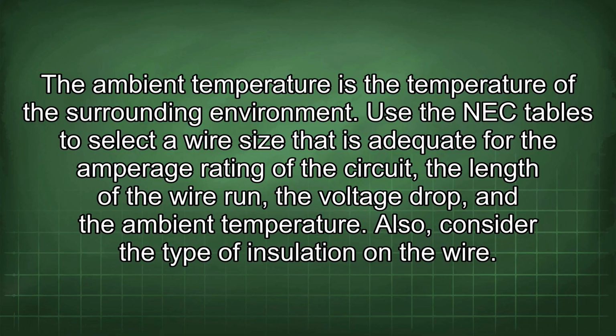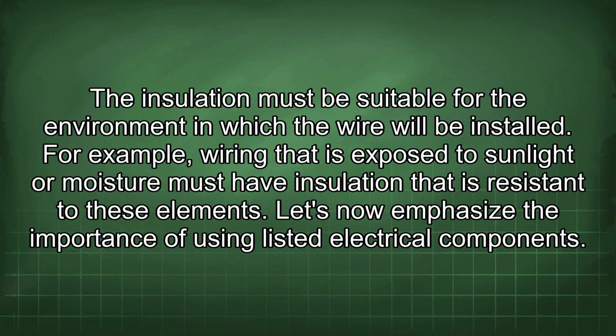Also, consider the type of insulation on the wire. The insulation must be suitable for the environment in which the wire will be installed. For example, wiring that is exposed to sunlight or moisture must have insulation that is resistant to these elements.